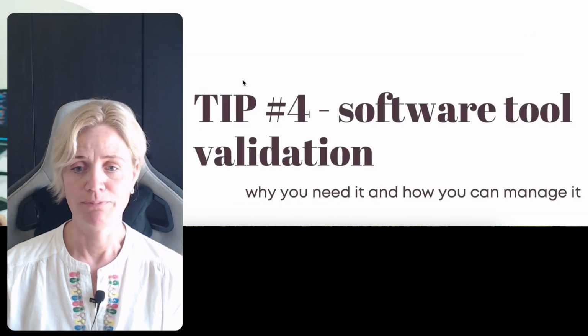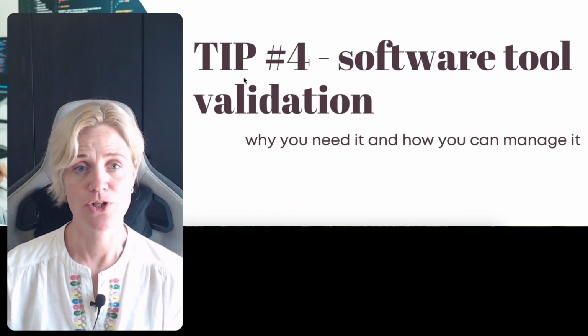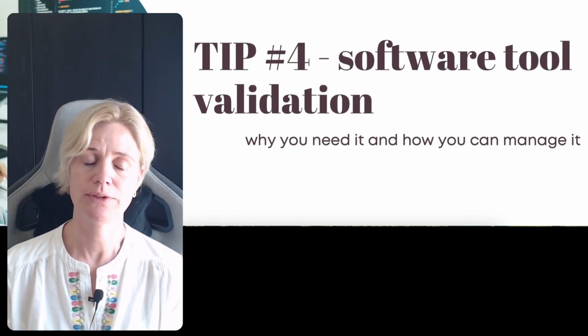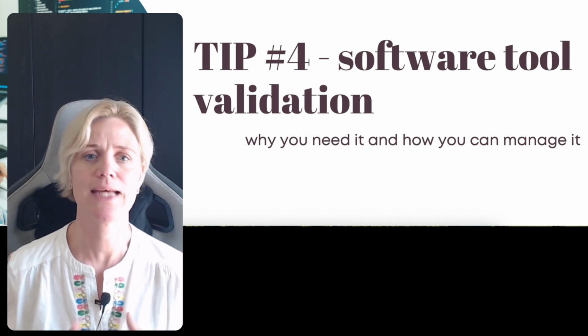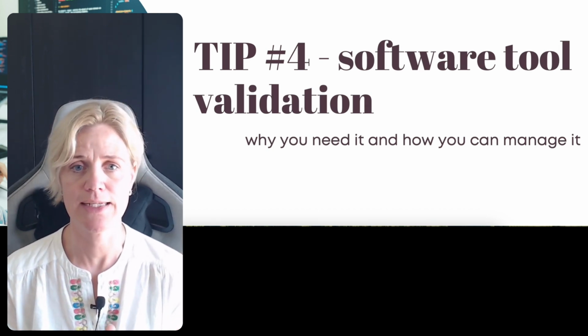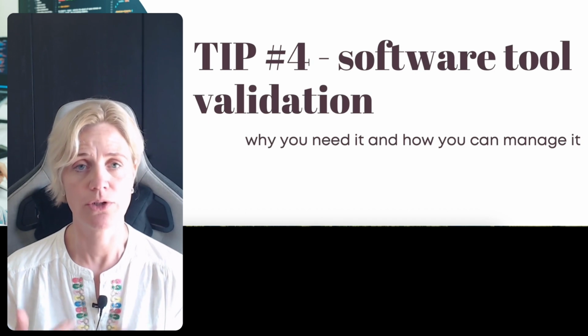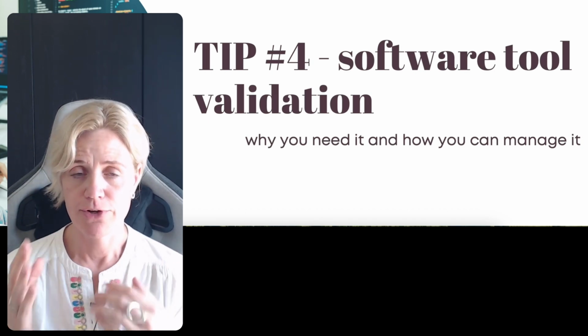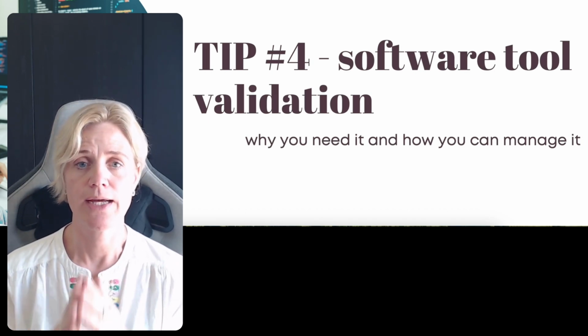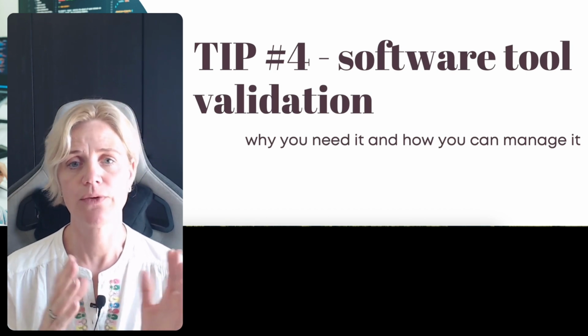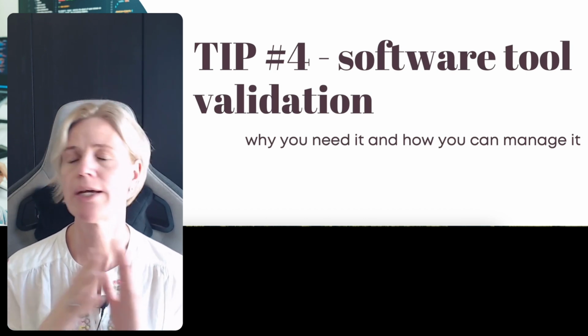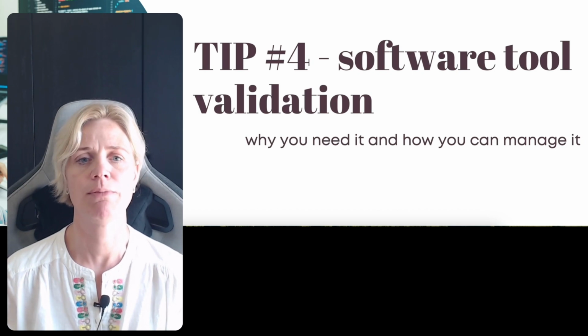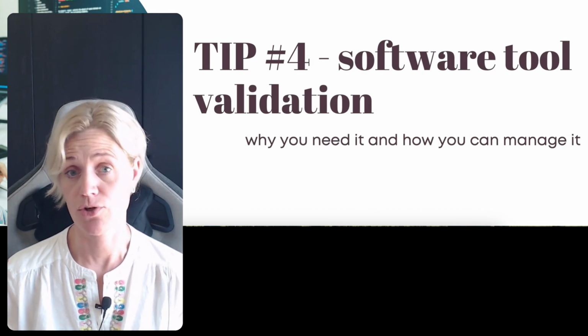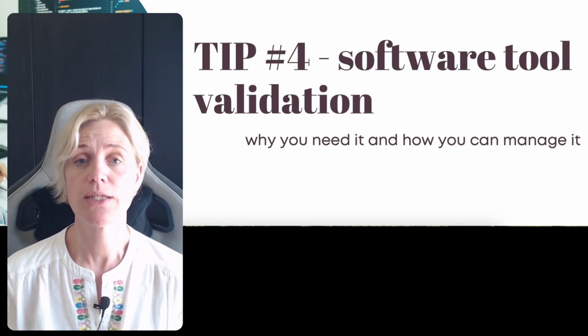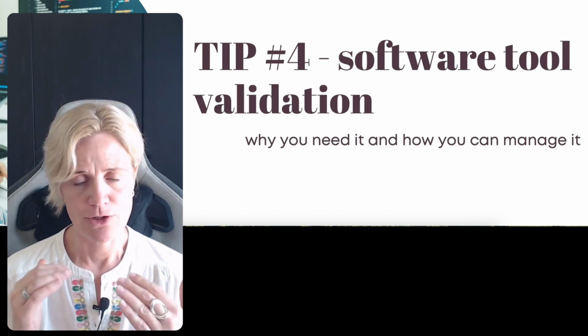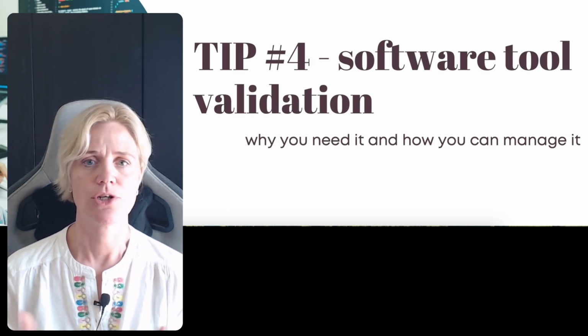Tip number 4. Really consider software tool validation, and it is manageable. Yes, Confluence, Jira, vulnerability scanners, debuggers, they all need to be validated if they impact your product or your quality system. But first think, what is the required approach to it? Start with a risk-based approach to validation. Don't try to validate everything all the time or validate tools that actually do not need to be validated. Adopt the risk-based approach, and you can learn all about that in validation guidance documents.